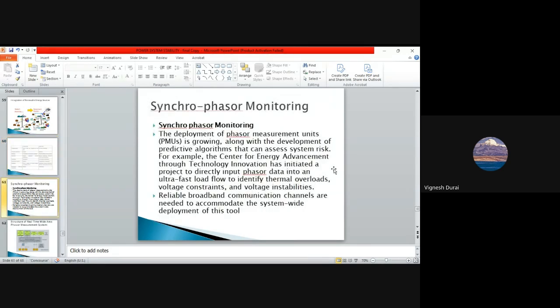See, this synchrophasor monitor, which we will call PMUs, is like a master checkup. If you want an analogy, it is like a master checkup. You have RTUs. Anyway, RTUs communicate through the line to SCADA. This PMU is like a master checkup which is done every second. You can do 48 master checkups like that, so your entire grid will be subjected to scanning every second. It will scan 48 times.